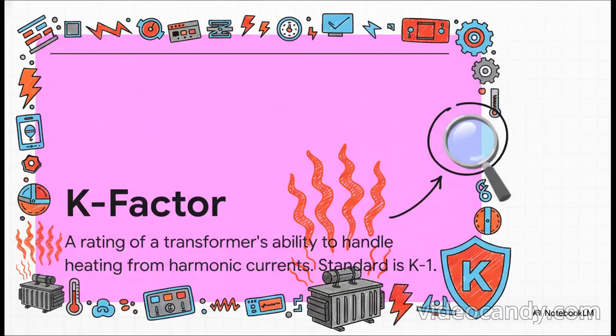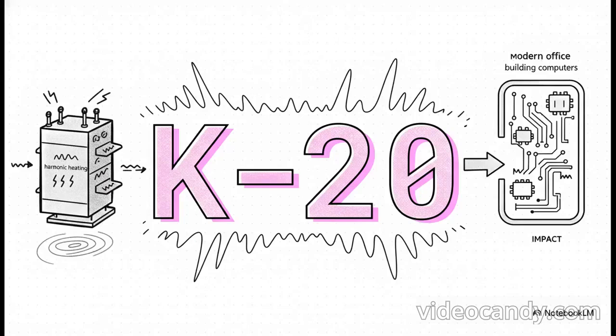And transformers, which were designed for that clean, smooth 60 Hz wave, really struggle with this static. It makes them vibrate and heat up in ways they're not supposed to, which causes a huge spike in those wasteful eddy current losses we talked about earlier. To fight back against this, engineers developed a rating system called the K-factor. It's pretty simple. It's just an index of how well a transformer can handle the extra heat that gets generated by all these harmonic currents. A standard transformer, one designed for old-school linear loads, has a K-factor of 1. That's our baseline.